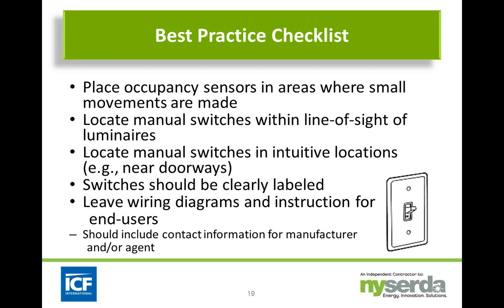You want to make sure that the manual switches are located within line of sight of the luminaires. Again, if you're dealing with passive infrared, they must be in line of sight to operate properly. They need to be in intuitive locations. I've seen applications where the layout of the space had changed, and the hinge on the door had moved. Now the doorway opens up and blocks the device. So you want to be very careful not to put the devices behind a door. That's not an intuitive place to find the switch, and it doesn't work if it's a passive infrared application.